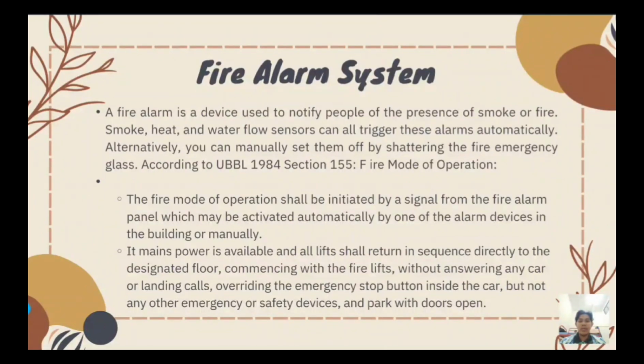According to UBBL 1984 Section 155, fire mode of operation. First, the fire mode of operation shall be initiated by a signal from the fire alarm panel, which may be activated automatically by one of the alarm devices in the building or manually. Second, if power is available, all lifts shall return in sequence directly to the designated floor, commencing with the fire lift, without answering any car or landing calls, overriding the emergency stop button inside the car but not any other emergency or safety device, and park with doors open.